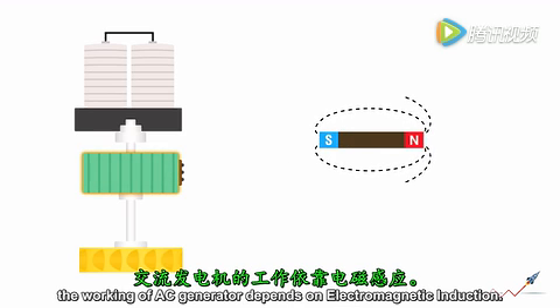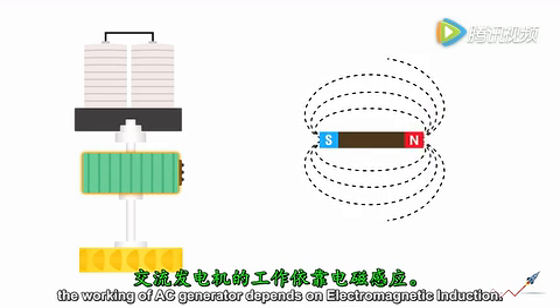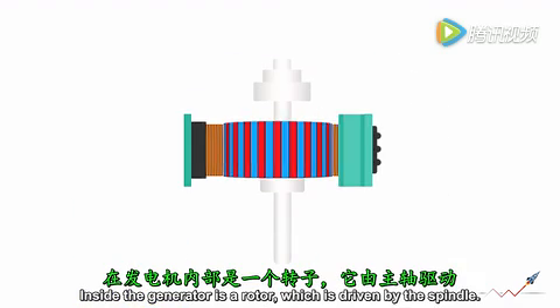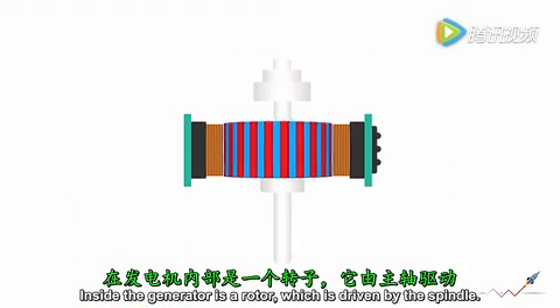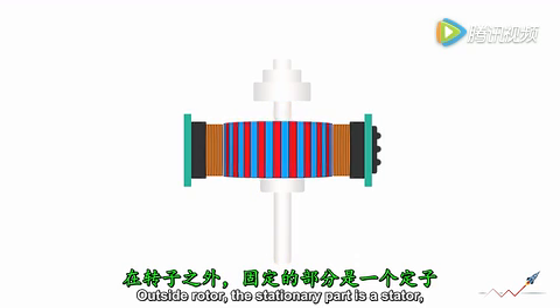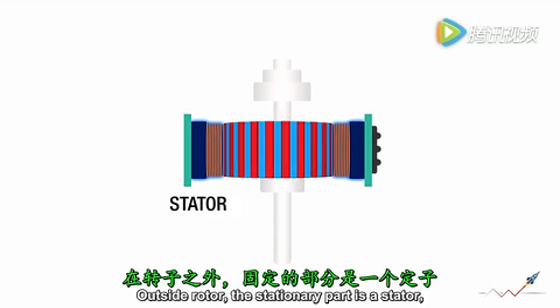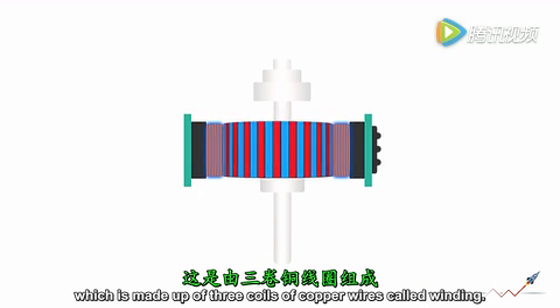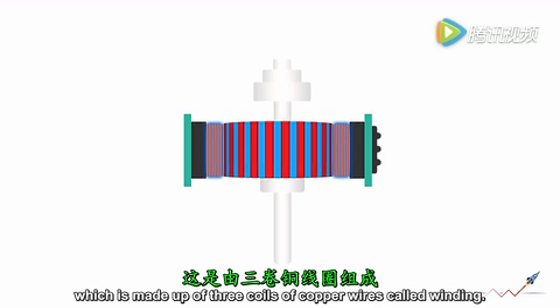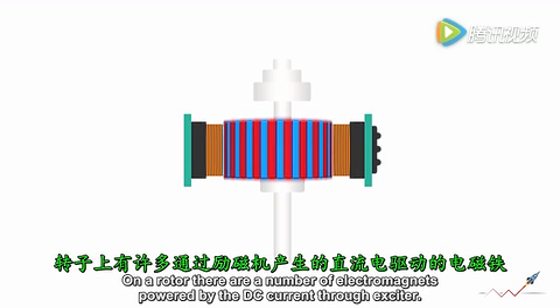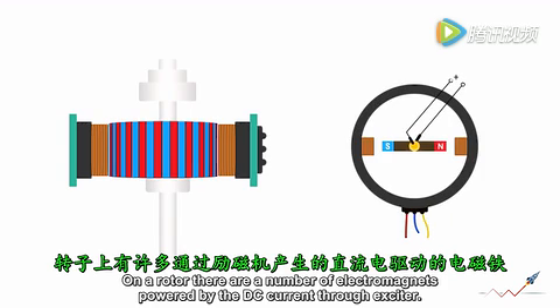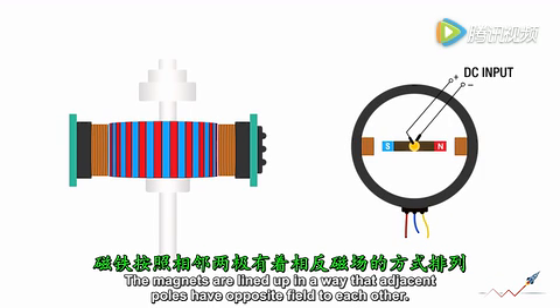The working of an AC generator depends on electromagnetic induction. Inside the generator is a rotor, which is driven by the spindle. Outside the rotor, the stationary part, is a stator, which is made up of 3 coils of copper wires called winding. On a rotor, there are a number of electromagnets powered by the DC current through the exciter. The magnets are lined up in a way that adjacent poles have opposite fields to each other.